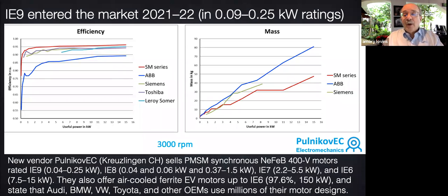GreenTechMotors.com claims a Boeing and NASA-derived lightweight 20 horsepower motor at 97.7%, pretty good. Maybe not as good as this PulnikovEC. Infinitum Electric's liquid-cooled air core motor substitutes a printed circuit stator disc for iron. So it saves about half the weight and 2/3 of the copper, albeit at lower efficiency than Polnikov, but maybe lower cost. And at this rate, IE10 can't be far off. There's just a lot of innovation going on. And it's a good thing the IEC rates efficiency by numbers, not words, because IE4 is already called super premium efficiency. I think 5 attracts a word like ultra, but you run out of superlatives pretty fast.